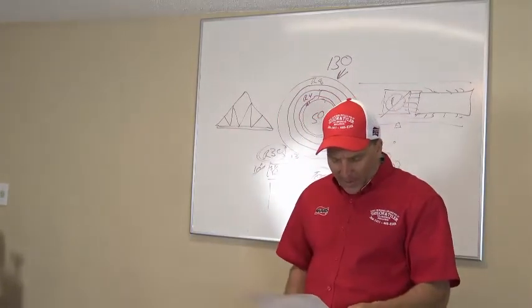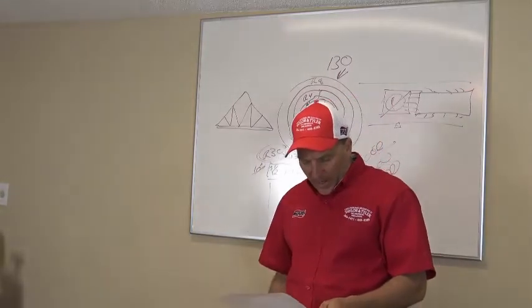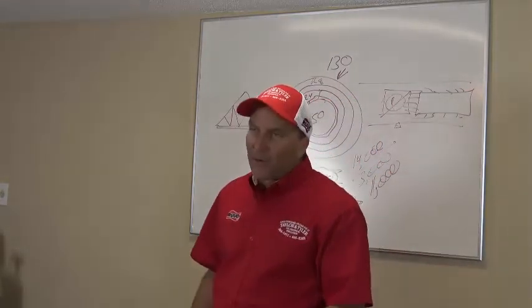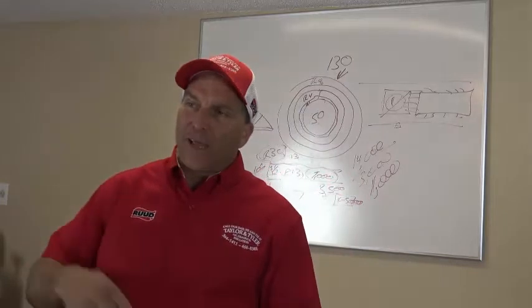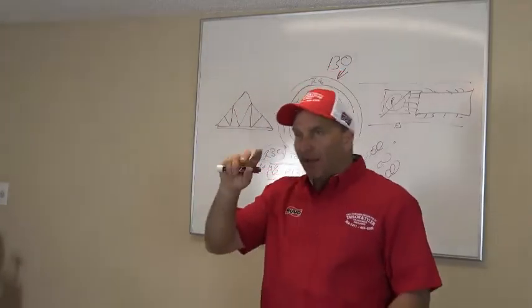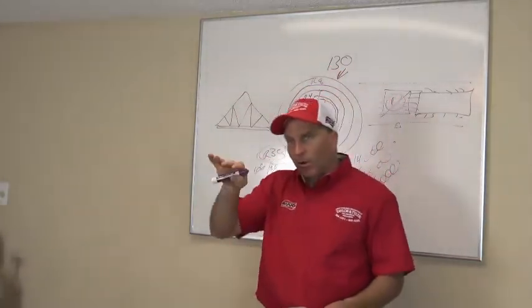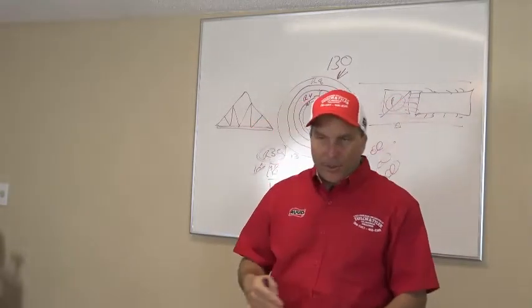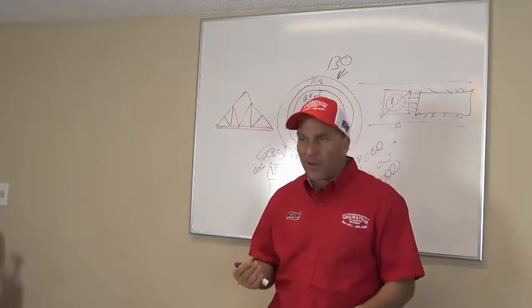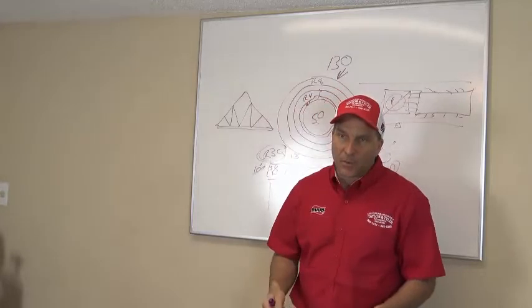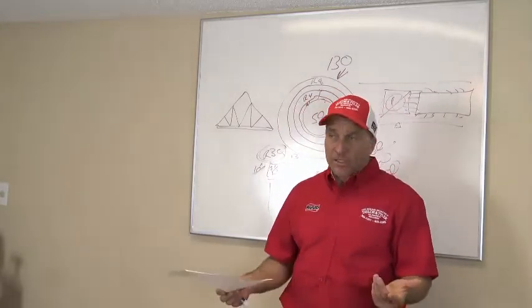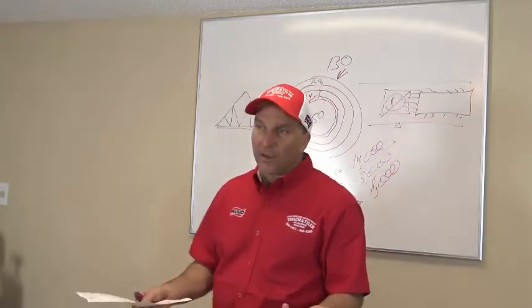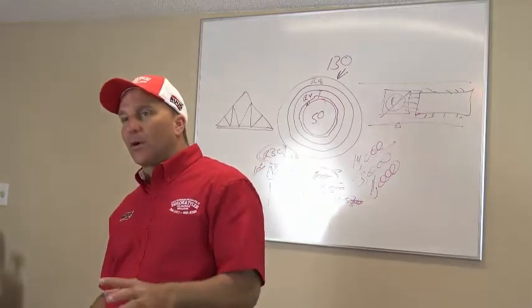Alright, we're down to the bottom, airflow. Thermostat. Okay, unlevel or broken. Unlevel is the biggest thing when you have the old analog thermostats where you got a little dial inside of it and you got the mercury bulb falling over. The digital thermostats don't matter if they're unlevel, other than the actual sight of them. Broken means that it just don't work. Or sometimes they're broken and hanging off the wall, or the cover's broken on them, that kind of stuff.